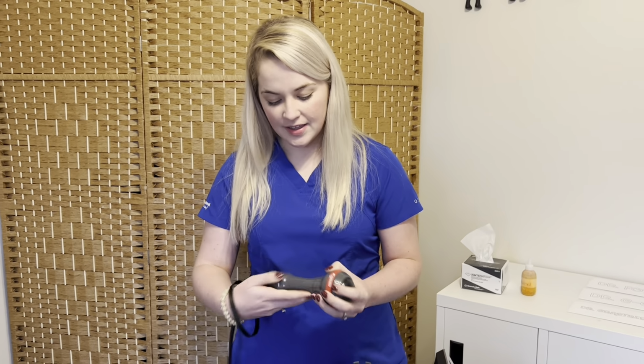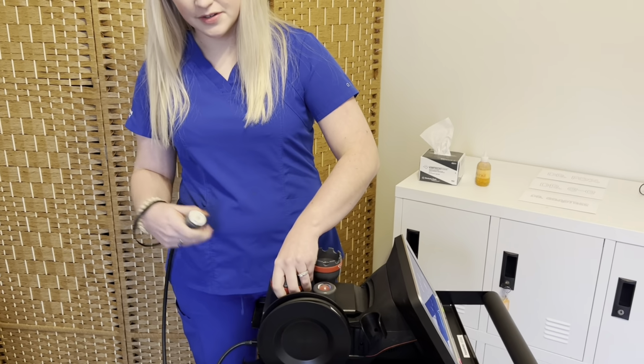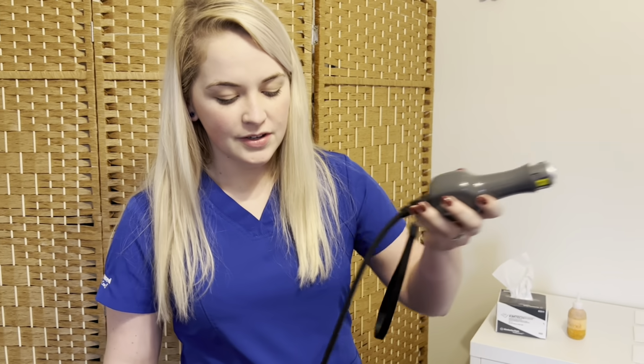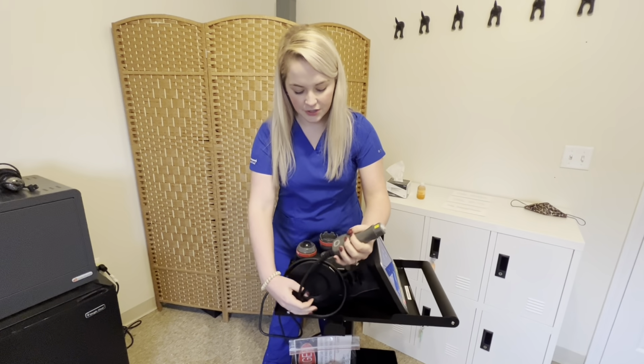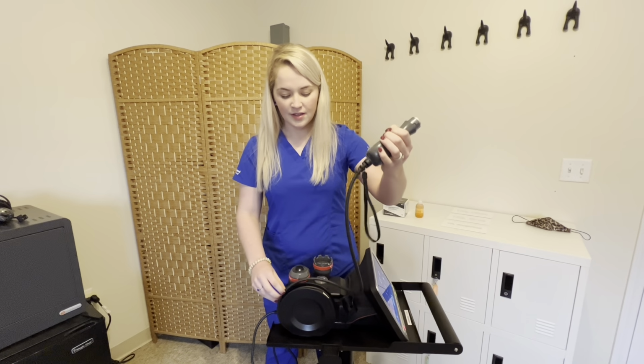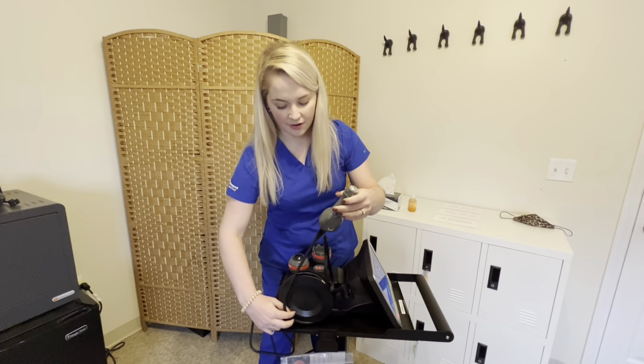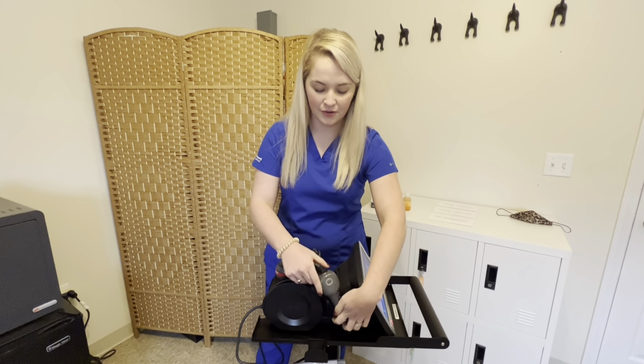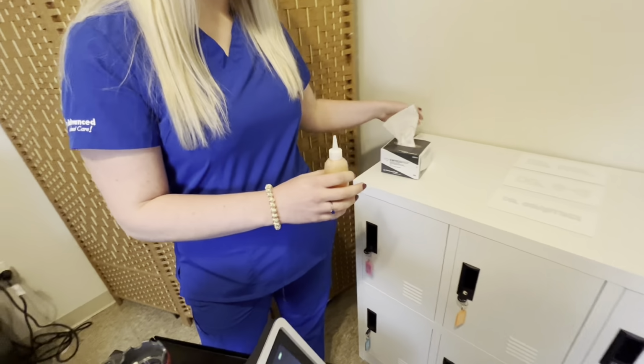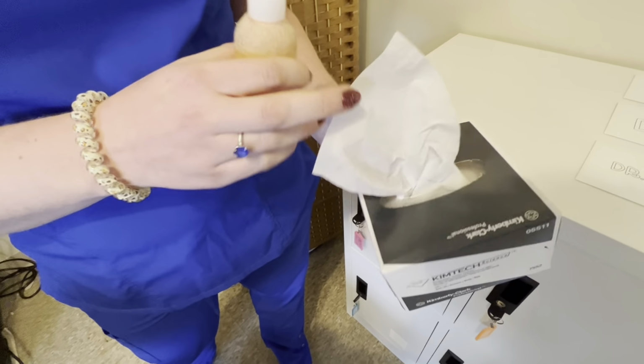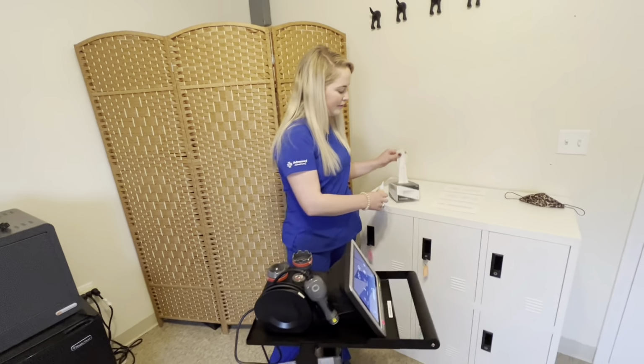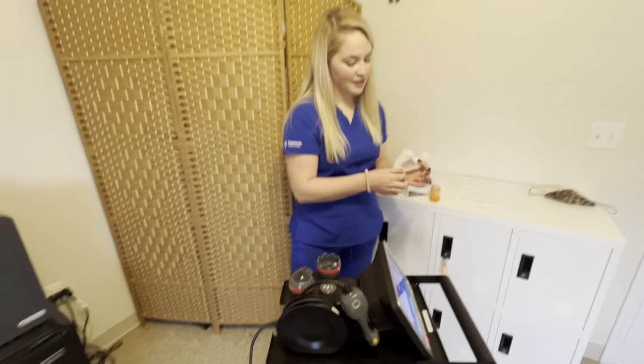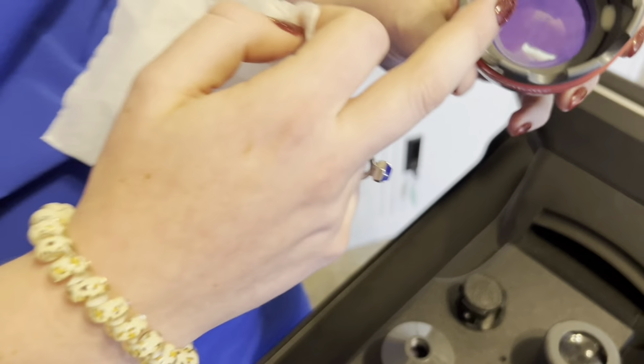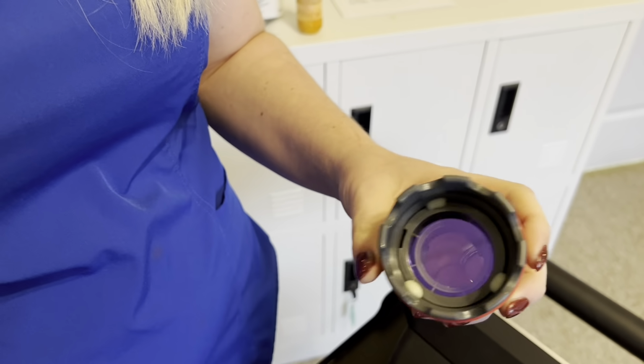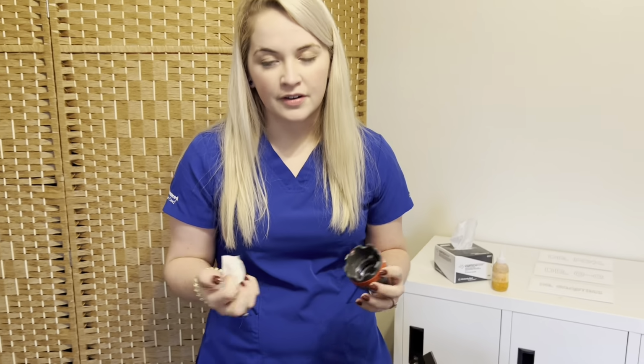As far as cleaning, in the past, after every usage, we had not been cleaning these treatment heads. So it is recommended moving forward that after each use we clean the heads appropriately. The solutions that we're going to use to clean the treatment heads are alcohol and Kimwipes. Everybody knows that the Kimwipes are housed next to the microscope. This is what the Kimwipes look like. It's the tissue-like material here. You'll use alcohol, take your Kimwipe, and put that on there. And then for these individual treatment heads, especially these, make sure that we're wiping down the surfaces and the lens very well. If debris is kept in here, hair, dirt, it can burn the lens and can actually cause damage to the treatment heads themselves.